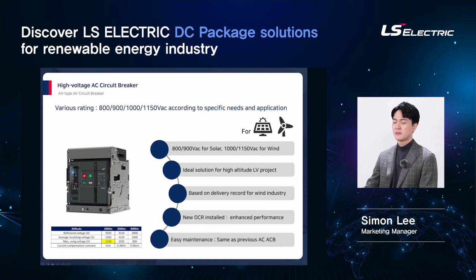As you might know, many PV projects are carried out at alpine zones more than 3000 meters above sea level nowadays. Our 4V-type ACB offers various ranges of rated voltage, so you could consider 800 and 900 volts for PV application in high altitude, and 1000 and 1150 volts products for high voltage ride-through feature of wind turbines.